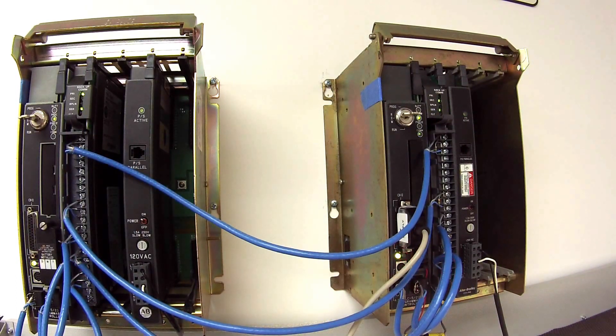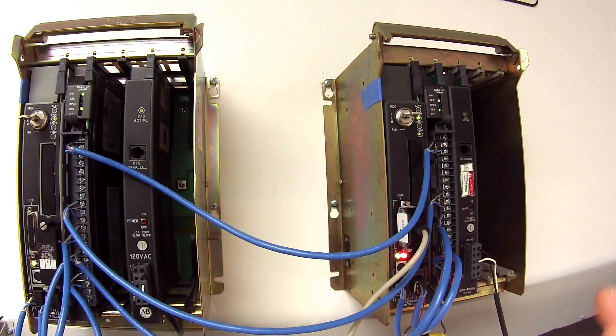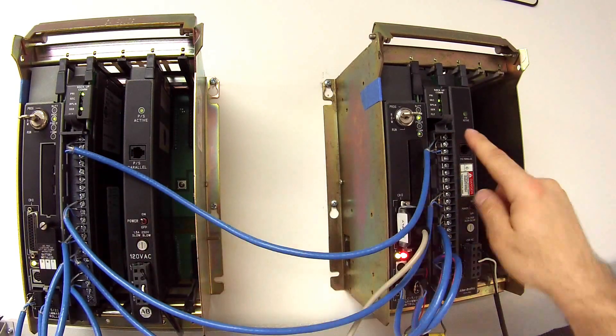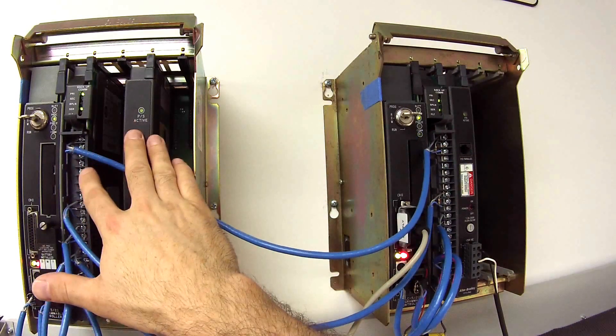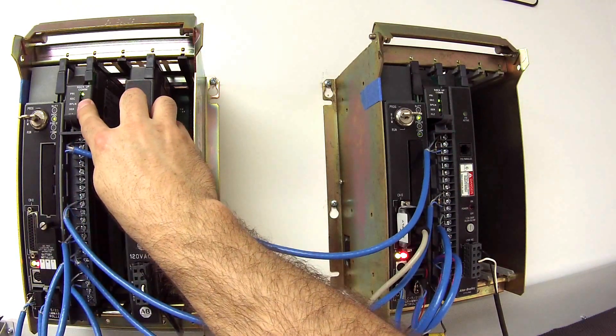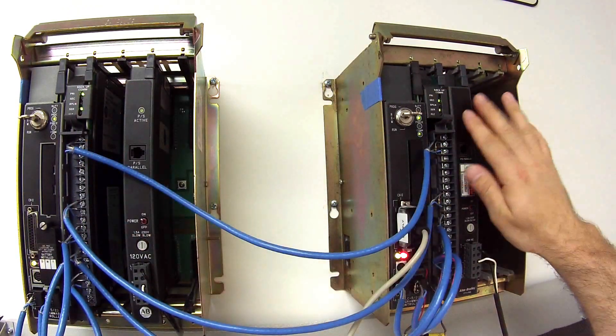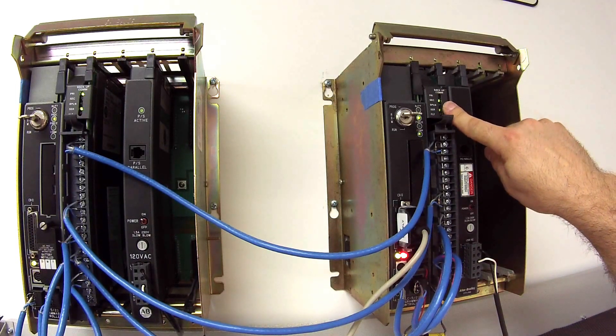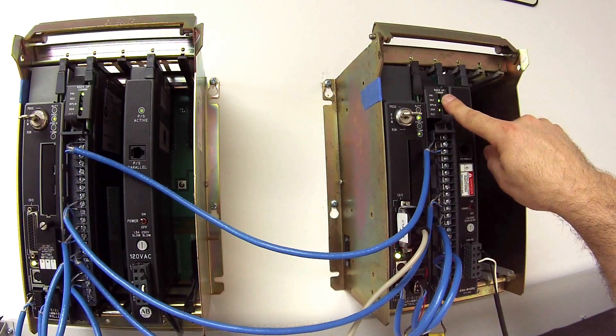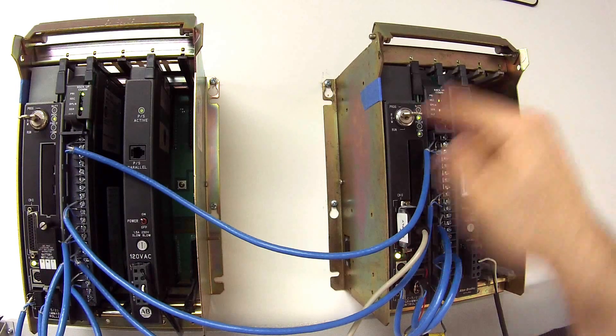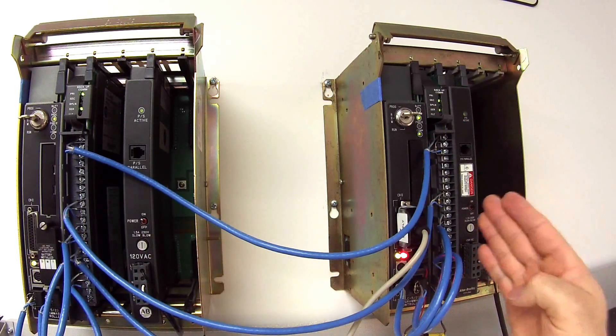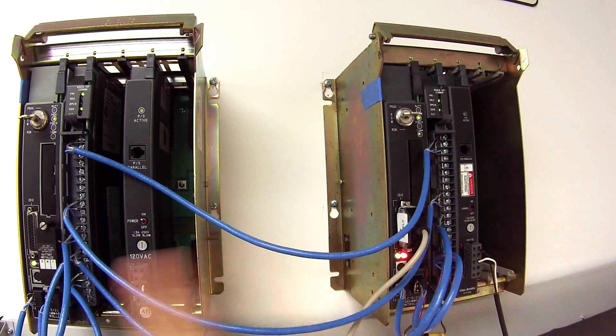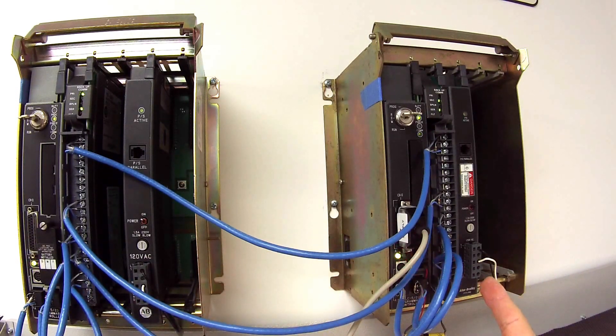The test will be basically testing the module's ability to pick up if one fails. So if this rack fails, which is currently in primary, then this rack or backup communication module should pop into the primary position and take over, and vice versa. This way I know that they're able to pick up when they're supposed to, number one and number two, that both modules are communicating with each other.